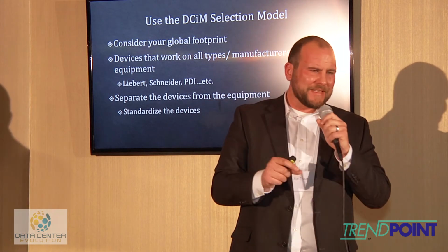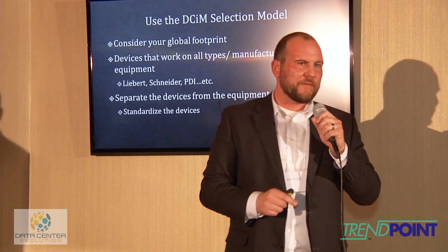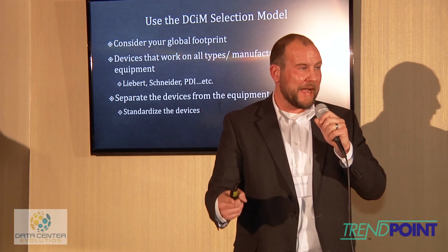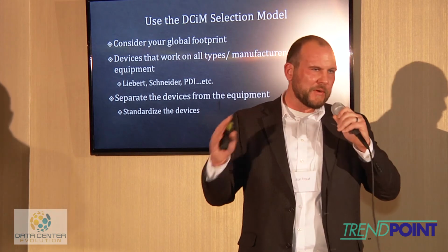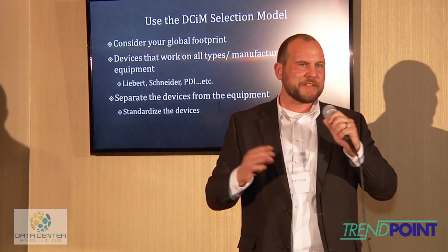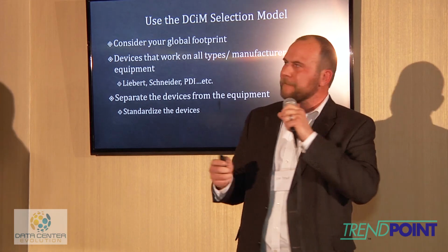And what we see a lot of times is data centers select a device that comes with the manufacturer's equipment. So if it's a PDI PDU, they'll use PDI metering. If it's a Liebert PDU, they use Liebert metering. If it's a busway, they use whatever the busway manufacturer provides with their product. And you end up with that disparate system with all these different protocols and data points and maps and drivers that have to be written for all this software, for all these hardware devices.